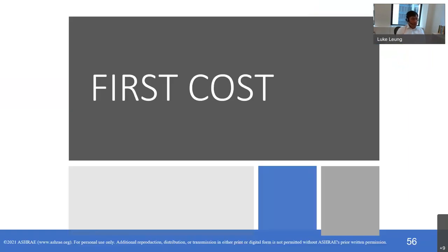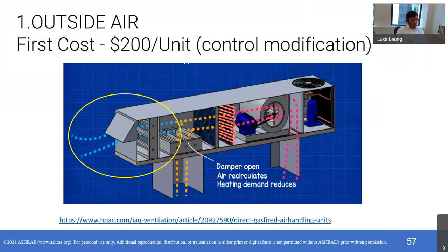Why do we say that? Let's look at first cost. Next slide. If you change the amount of outside air, the first cost could be really low, provided your coils have capacity. You just change the damper position through the BAS. That could be a $200 sort of change if the system has the capacity. So it's relatively low first cost, but high operating cost. Next slide.